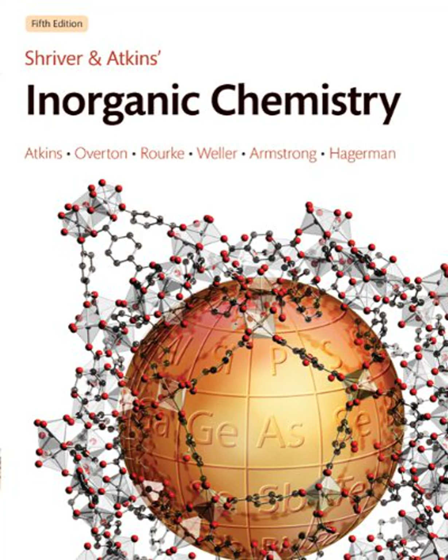Very sensitive. Especially with graphite furnace atomization, GFAAS, you can reach detection limits down to parts per billion, or even parts per trillion for many metals. Almost every metallic element can be determined this way. Okay, another classic. CHN analysis for carbon, hydrogen, and nitrogen. A workhorse technique. You take a tiny, precisely weighed amount of your sample and combust it completely at high temperature, around 900 degrees C, in a stream of pure oxygen.